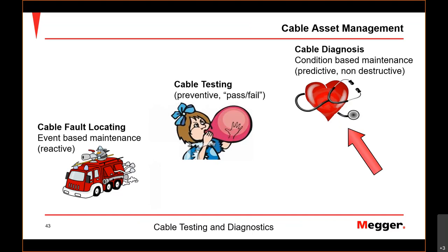Cable testing is basically just a yes or no test when there is a weak spot in the cable. I don't want to talk about a cable fault, just a weak spot. Because the fault is not here, hopefully, but the cable might be aged and we want to check in what condition it is. You could do this with a test, put overpressure onto the cable and either it fails or it holds if there is a weak spot.